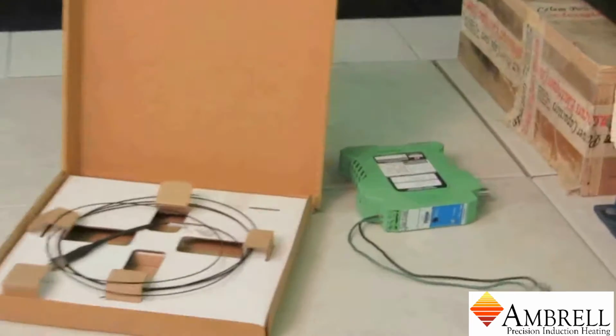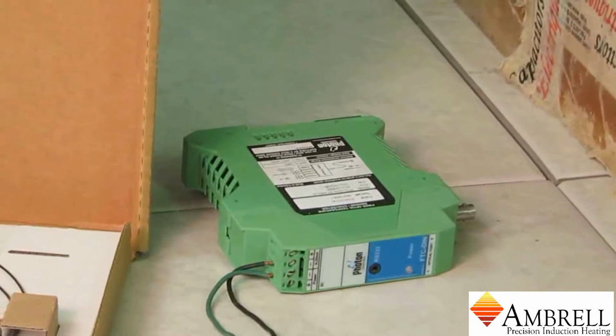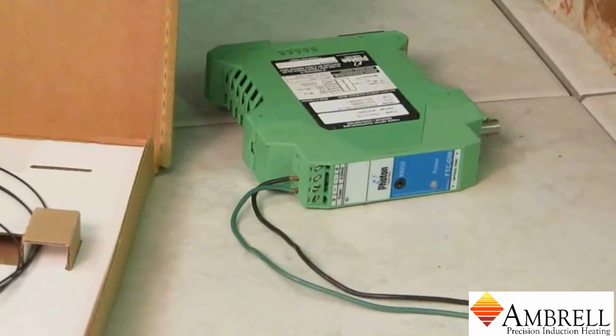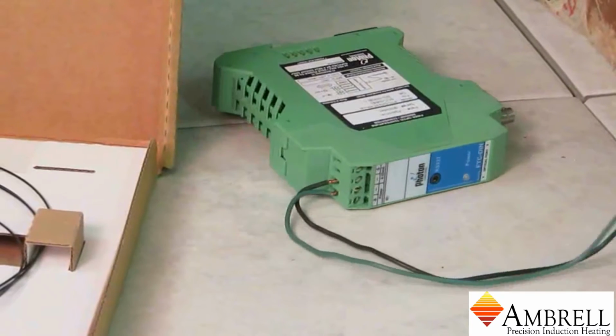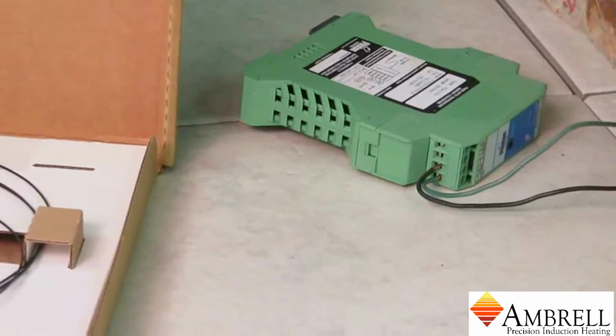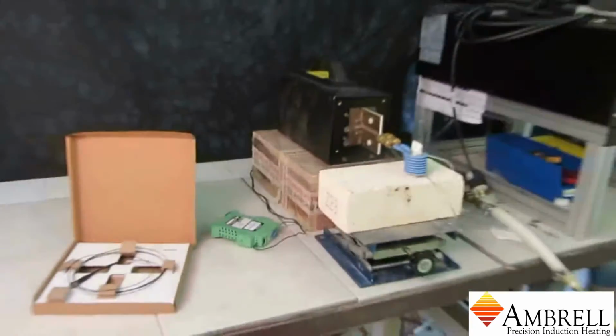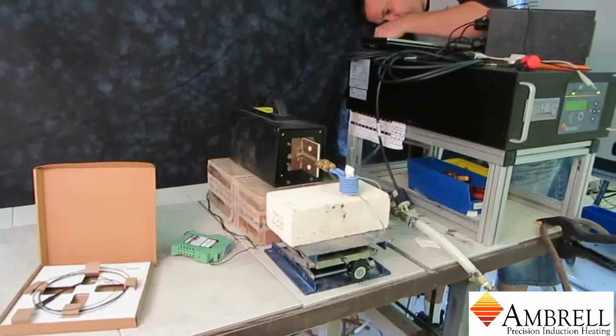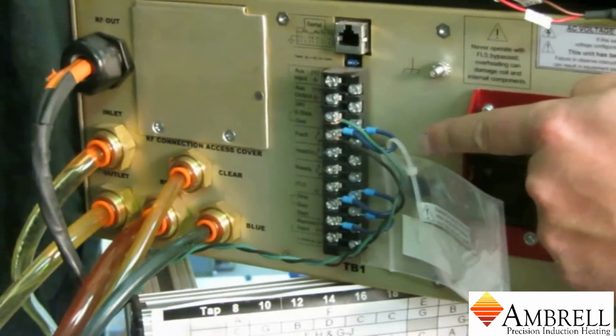You can see the unit there. And since for this demonstration we are using an Easy Heat Large, we'll be using the power off the back of the Easy Heat. Those two wires connect to the terminals that state 24 volts positive and ground. It's on the side legend that's right there.